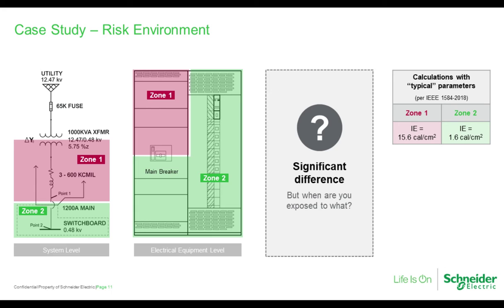Let's start, on the left side of your screen, with a one line of a 1,000 kVA 480 volt system, including the main transformer and downstream switchboard. In addition to the one line diagram, it's been color coded with incident energy levels calculated per IEEE 1584, corresponding to roughly the line side of the main circuit breaker and the load side circuit breaker.